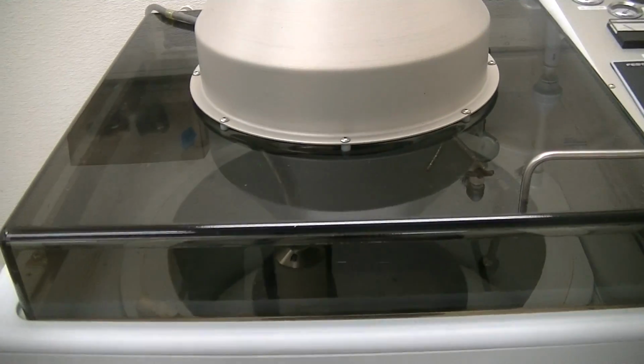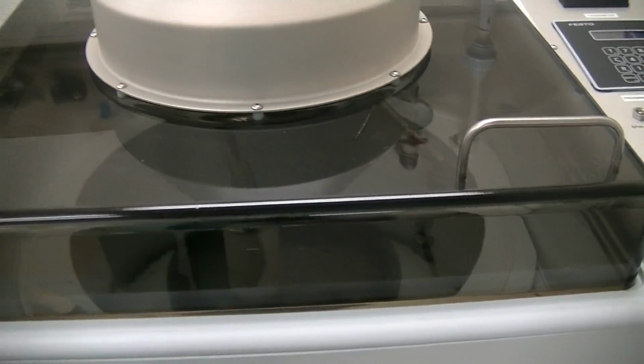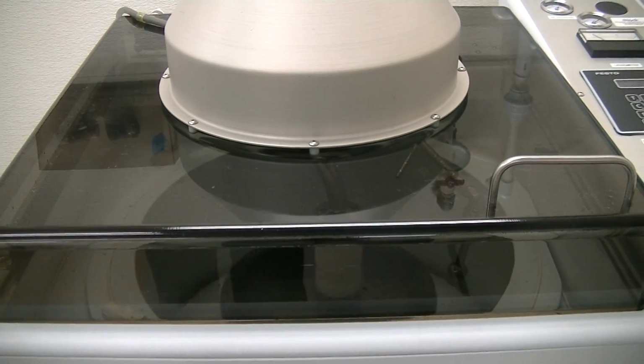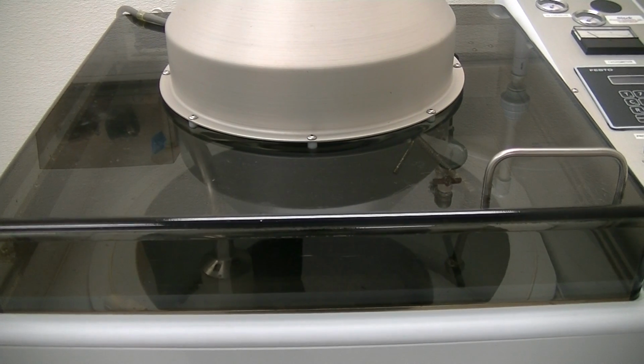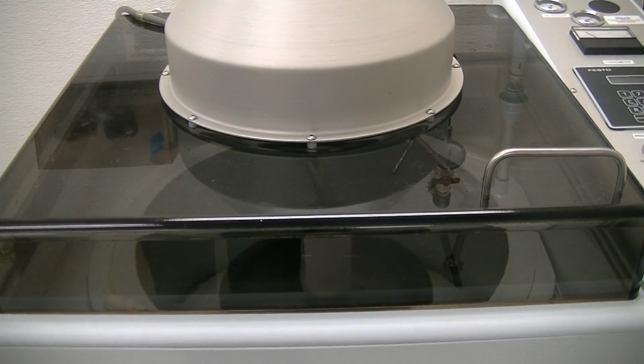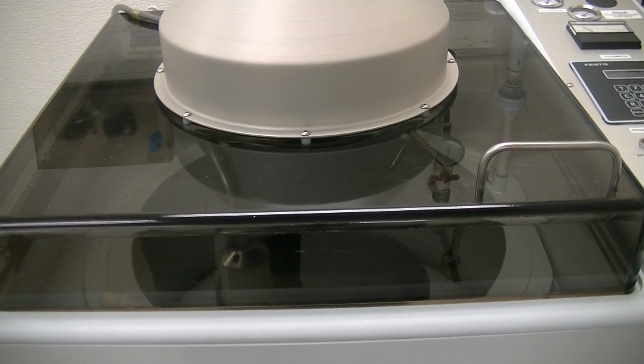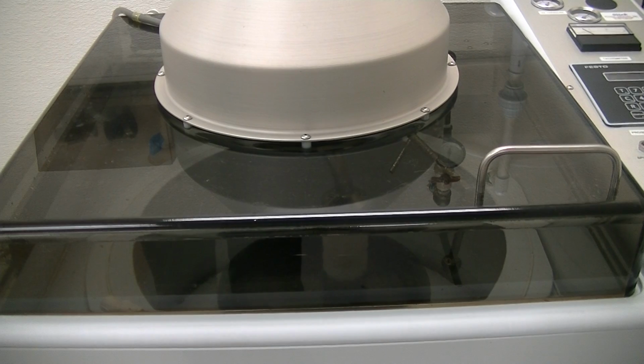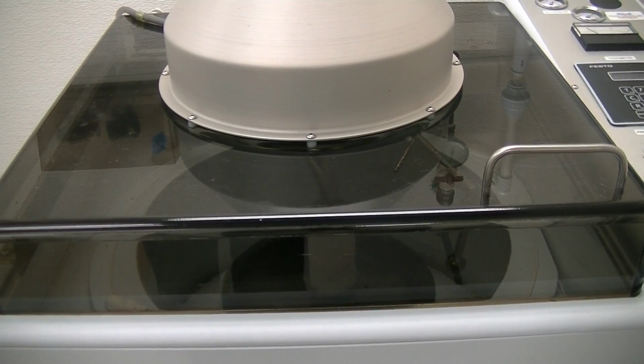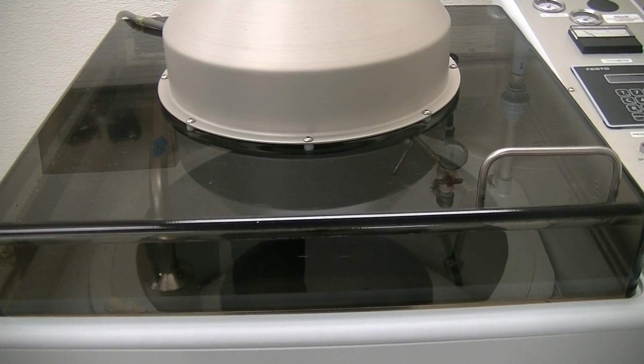Alrighty? And you can see the brush cycling back and forth. It's moving back and forth, dispensing as it's scrubbing. This system, as I discussed, has 2 pre-dispenses. So we have a dispense 2 programmed in, which will happen right after dispense 1. It won't look any different. It's just the chemical is coming through a second dispense that's integrated into the brush head assembly. All right.